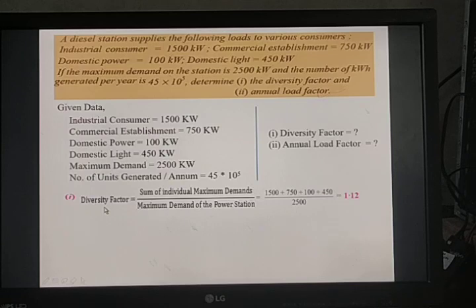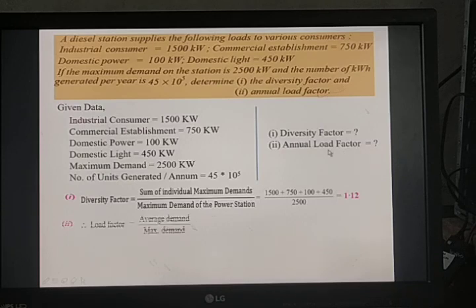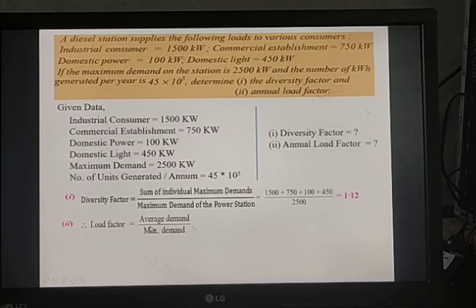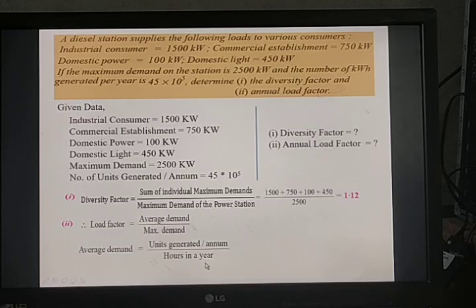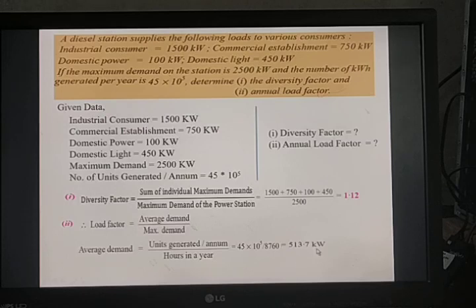The load factor is defined as average load divided by maximum demand. First, find the average load: units generated per annum / hours in a year = 45 × 10⁵ / 8,760 = 513.7 kilowatt.